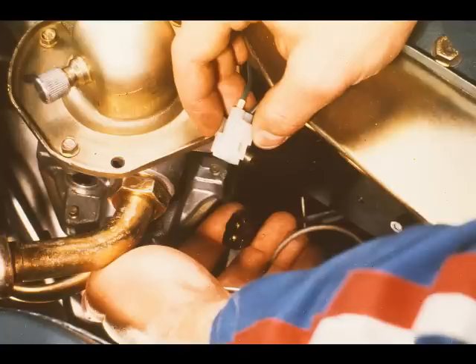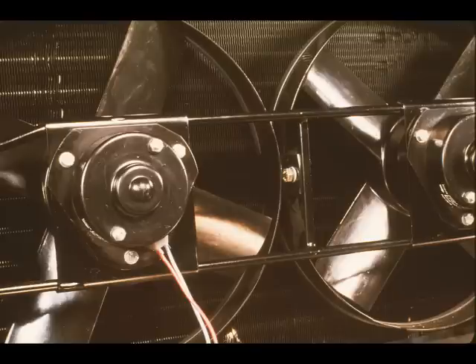Next, the cooling fan circuit. Disconnect the high-pressure switch and bridge the female connector. This will energize the cooling fan relay and the fans should operate. If the fans do not operate, suspect the relay and check it by substitution. It is unlikely that both fan motors would fail simultaneously.